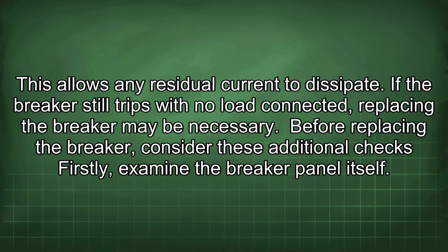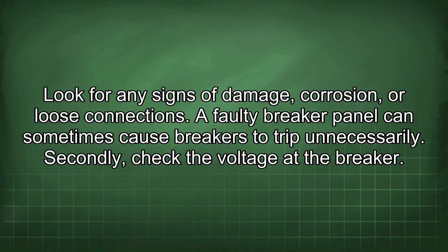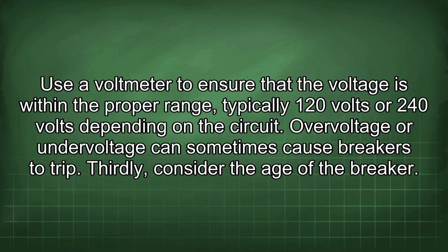Before replacing the breaker, consider these additional checks. Firstly, examine the breaker panel itself. Look for any signs of damage, corrosion, or loose connections. A faulty breaker panel can sometimes cause breakers to trip unnecessarily. Secondly, check the voltage at the breaker. Use a voltmeter to ensure that the voltage is within the proper range, typically 120 volts or 240 volts depending on the circuit. Overvoltage or undervoltage can sometimes cause breakers to trip. Thirdly, consider the age of the breaker.